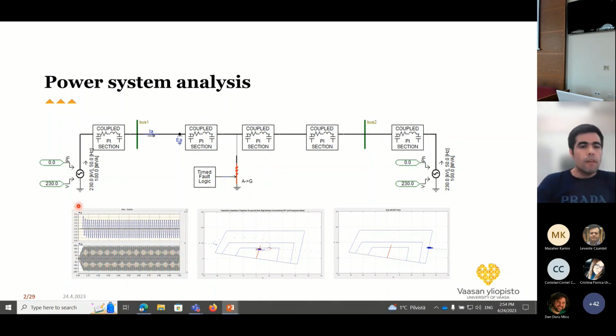It is a simple example from a 230 kilovolt power system in which we have substation number 1 and substation number 2. In this simple power system, we have an earth fault, which is a connection of one of the phases to ground, and this connection is a permanent connection, which is known as an earth fault. Since we have digital relays in this substation, we can detect current and voltage, and based on a simple equation, I mean dividing EA by IA, we can calculate the impedance of the system. The impedance trajectory in distance relays is like this, which shows that this earth fault occurred in the first zone of the power system.